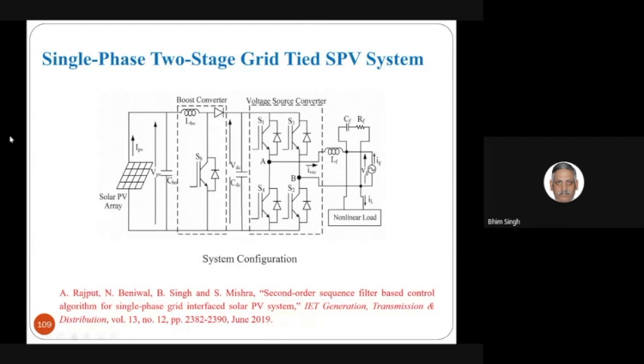And as far as losses are concerned, apart from the losses in the boost converter, the losses in the inverter are reduced because you are now allowed to change the DC link voltage, since this does not affect the MPPT. Your MPPT is done from the boost converter. So if the DC link voltage of the inverter is allowed to vary, the losses in the complete inverter are reduced, by a much larger amount. Typically here the loss is around 1.5%, while the loss reduction in the voltage source converter was typically around 4%.